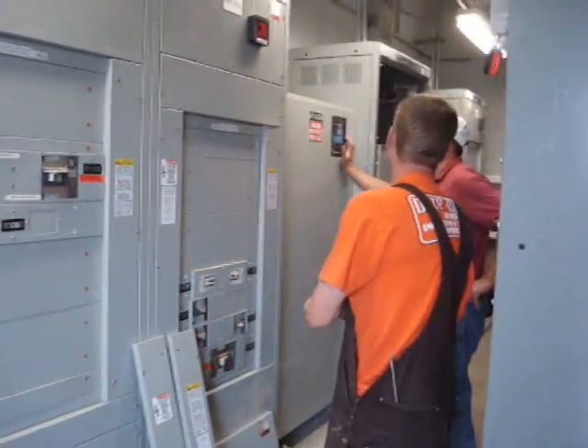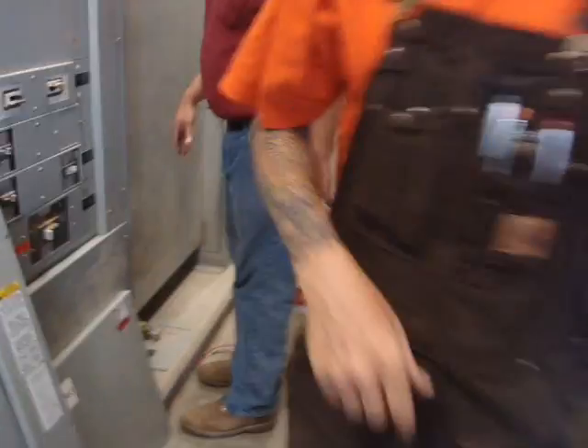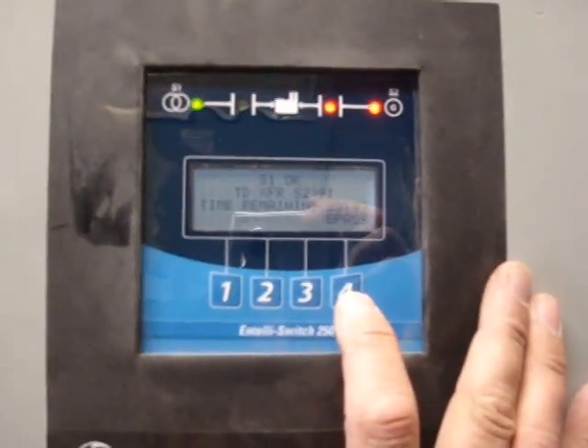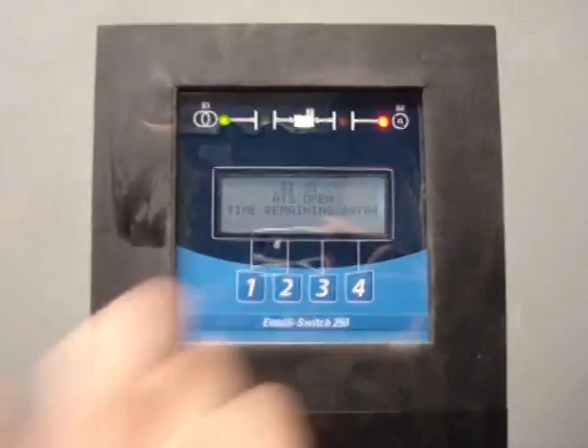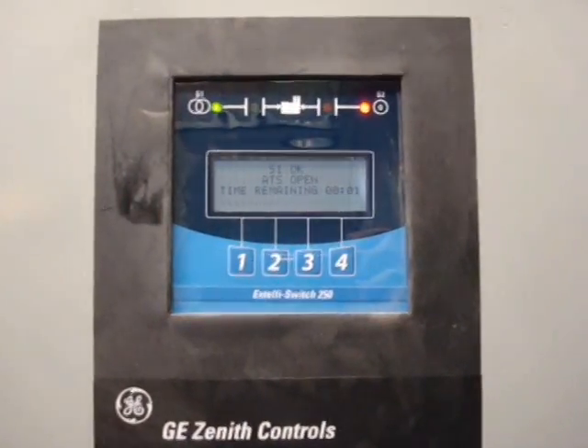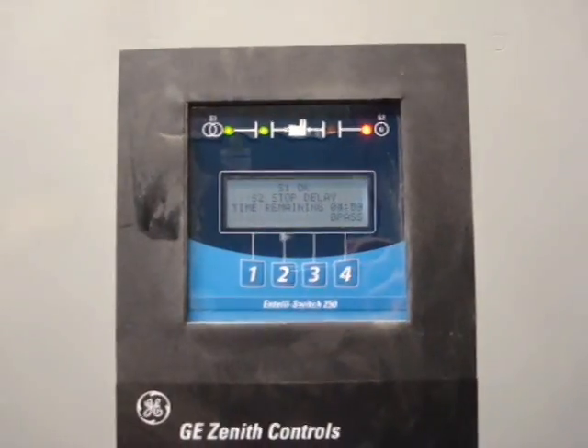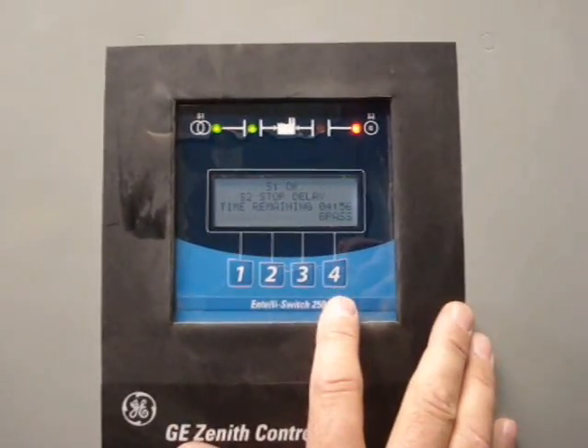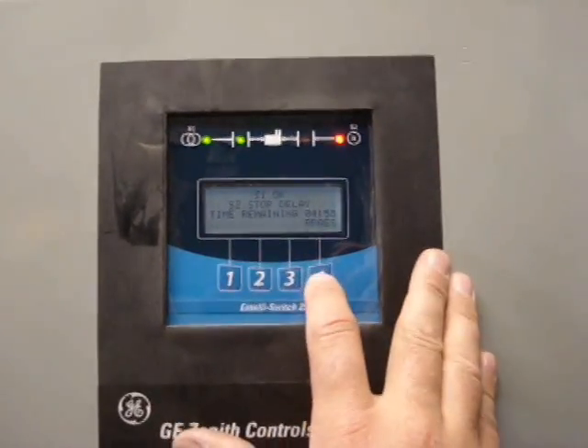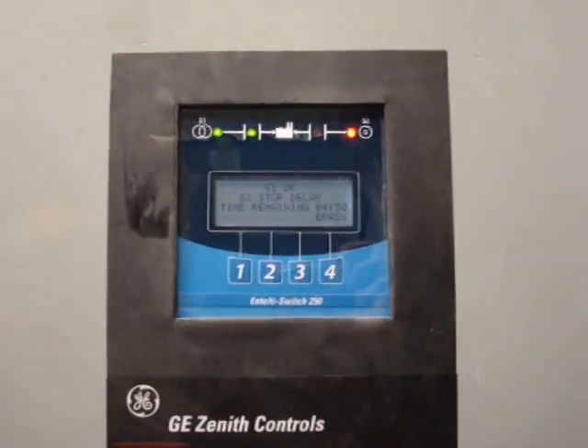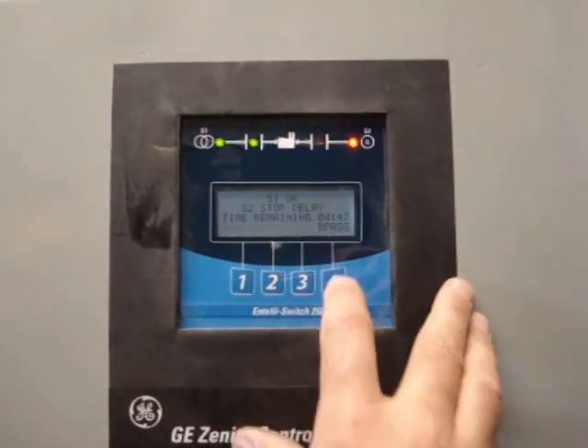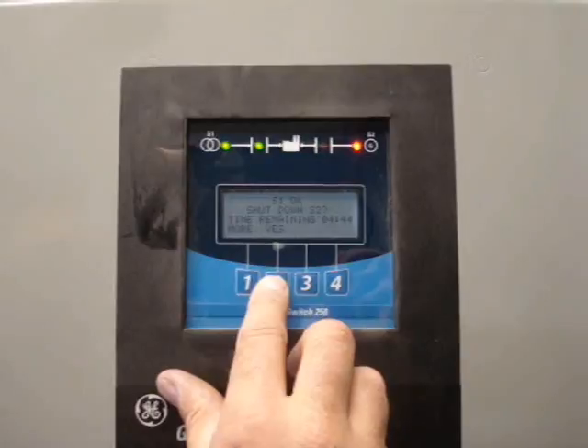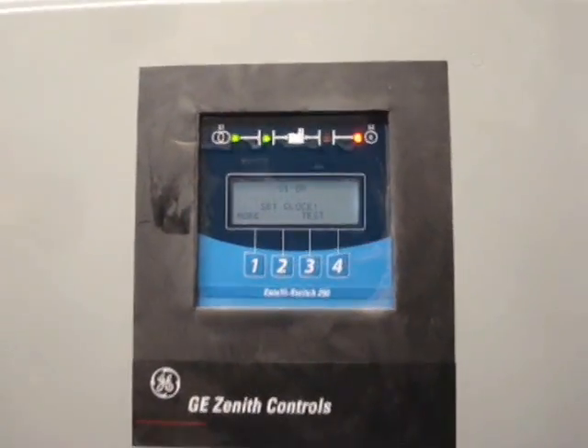Alright, now it's saying 30 minutes to bypass. We don't want to wait 30 minutes to transfer, so I'm going to hit bypass. And then it'll transfer in 3, 2, 1, transfer. And transfer. Right now we're on normal power with generator power available. What I can do is hit bypass, that'll shut off the call for the generator, or it'll time out. Generator just went off. Okay, looks good. That was for S1.